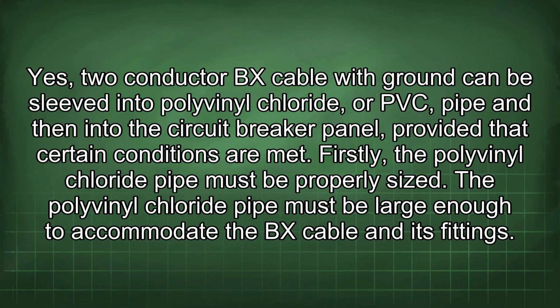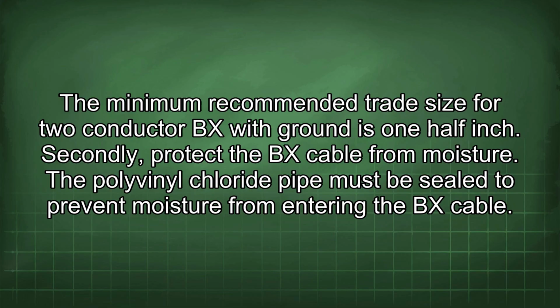Yes, two-conductor BX cable with ground can be sleeved into polyvinyl chloride or PVC pipe and then into the circuit breaker panel, provided that certain conditions are met. Firstly, the polyvinyl chloride pipe must be properly sized. The polyvinyl chloride pipe must be large enough to accommodate the BX cable and its fittings. The minimum recommended trade size for two-conductor BX with ground is 1/2 inch.